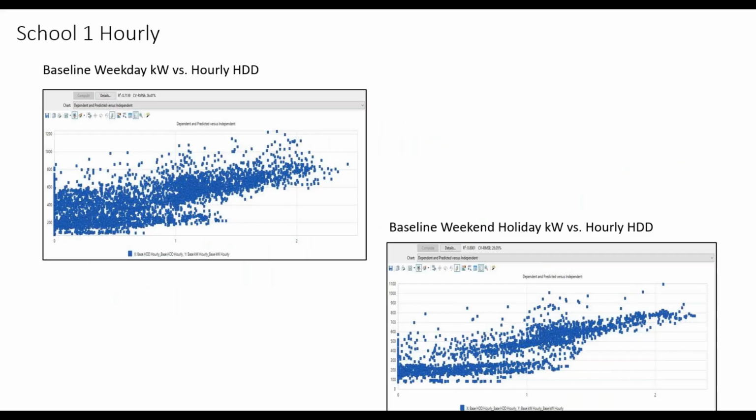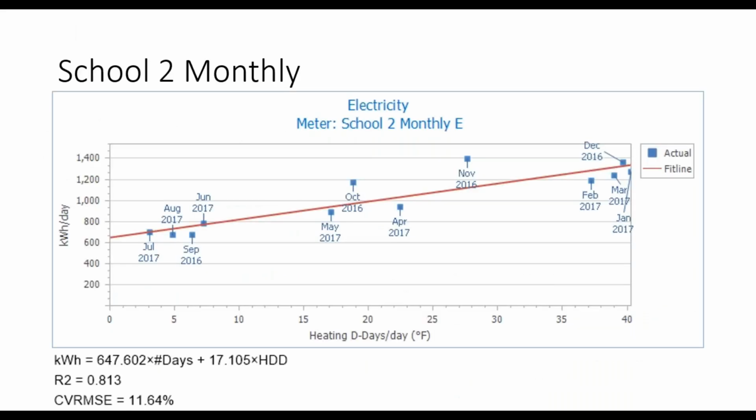So then we did hourly, and we broke this up into two groups: one regression for weekends and one for weekdays. They shouldn't be together. Next, and we'll stack all the results up in a table in a couple minutes. So we did another school, again, good fit. These ones didn't use the school days variable. So apparently, because they don't use a school days variable, they run the schools, this is in New York, the same whether people are there or not. I guess the lights are on all day, I guess the HVAC's on all day. At least that's what this says.